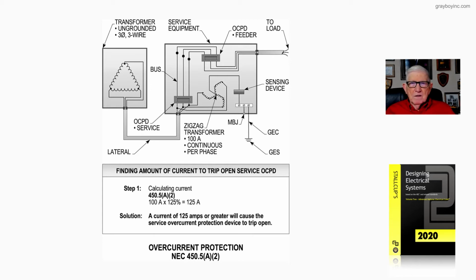In our book, Stallcup's Electrical Design Book, Volume 2, page 20-10, we start with the topic head, Grounding Auto Transformers, 450.5, and we just give a good introduction there. Then we start breaking it down. A 3-wire circuit to a 3-phase 4-wire circuit, 450.5(A) would deal with that. Connections, making our connections, 450.5(A)(1). Overcurrent protection, explaining the overcurrent protections and the benefit of where you place the overcurrent protection, 450.5(A)(2).